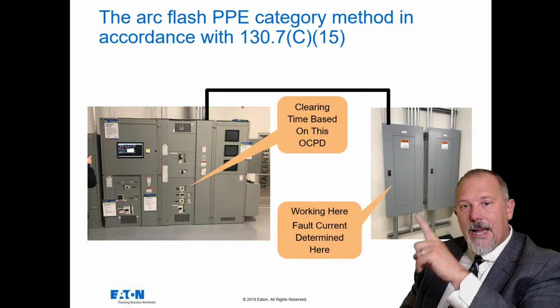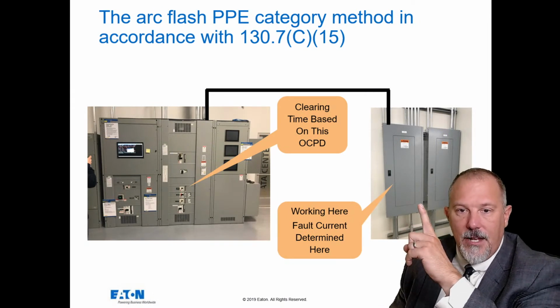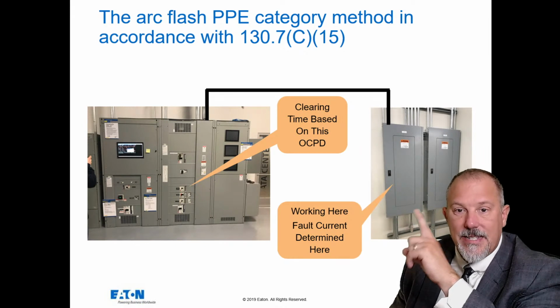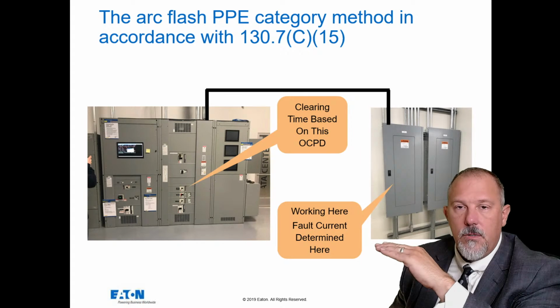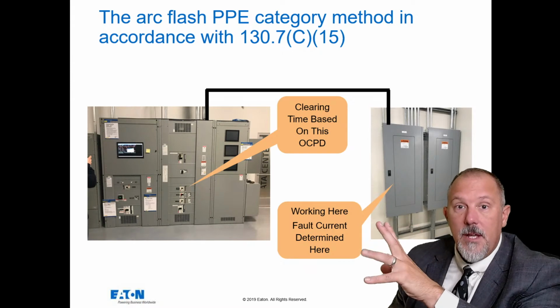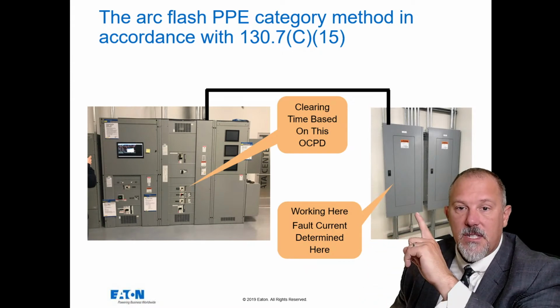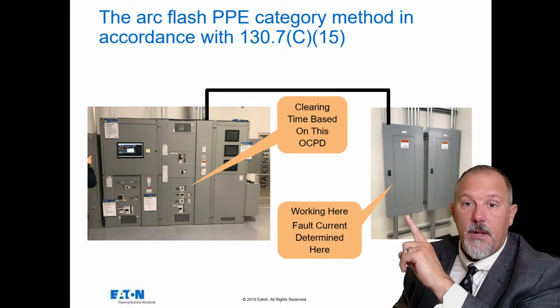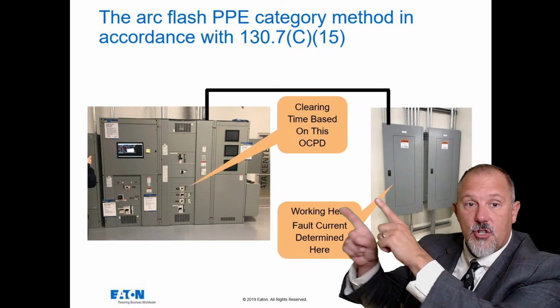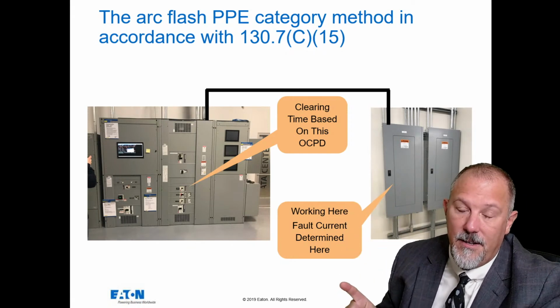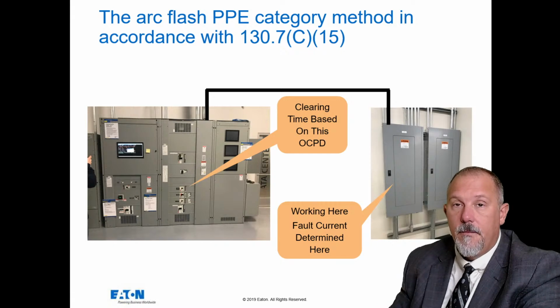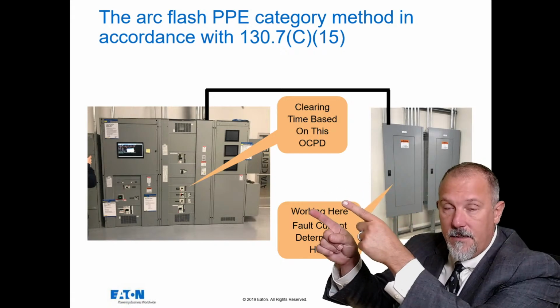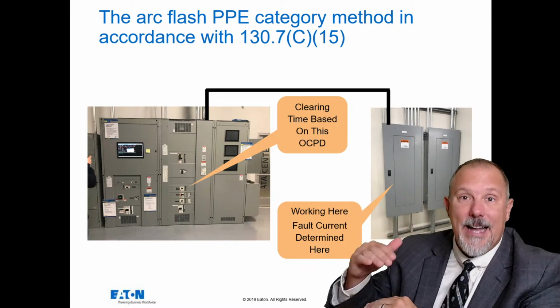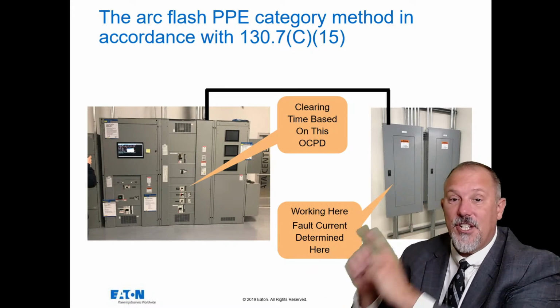For example, if I'm in this piece of equipment and I am series rating the main overcurrent device with a branch device in this equipment, that has nothing to do with the arc flash energy determination in this equipment. Because my incident energy is not based upon the main device in this equipment. It's based upon the feeder upstream in that other bigger gray box that is feeding this panel, the clearing time of that device at the lowest and highest arcing current.